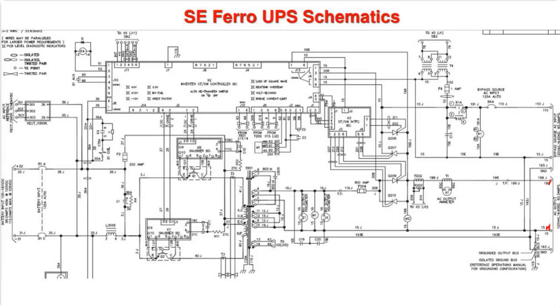The only other thing that I'll mention is here's our bypass coming in here, 120 volts, single phase. Then here is our bypass AC input breaker. And you see here that we have a contactor, K1, connected across the input to the system. As soon as you close this bypass source AC input breaker, this coil should energize and pull in the contacts related to this coil here. So basically, it's allowing the voltage to get to the bypass static switch.